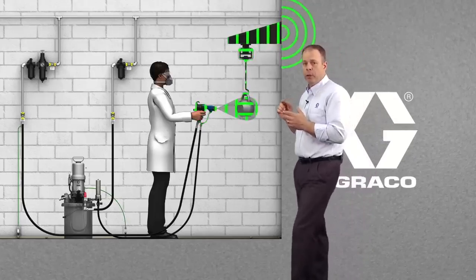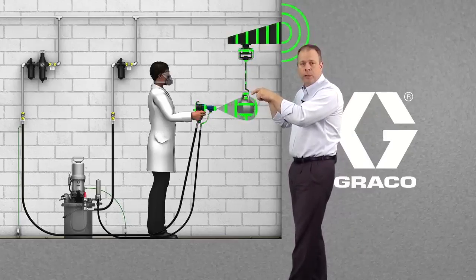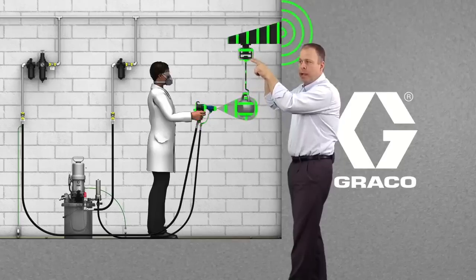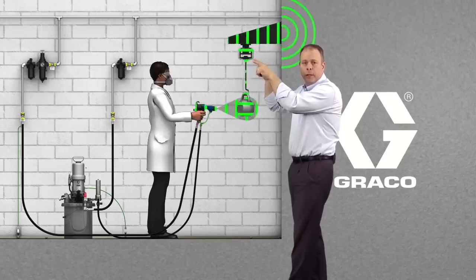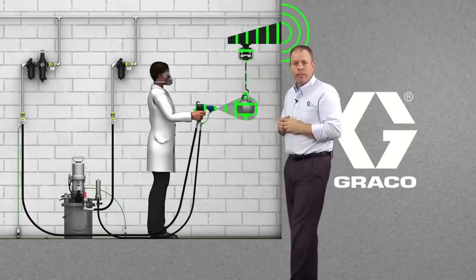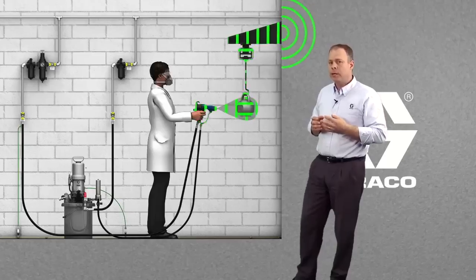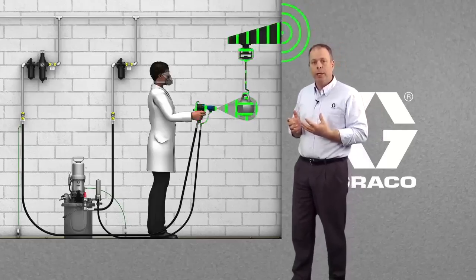Some of the points on here that we should look at and consider is the first one is where the hook connects to the part. And then the next major concern is where the hook connects to the conveyor. There tends to be some paint overspray in this area, and if I get too much paint overspray, then that starts isolating the part and I don't get that good ground.